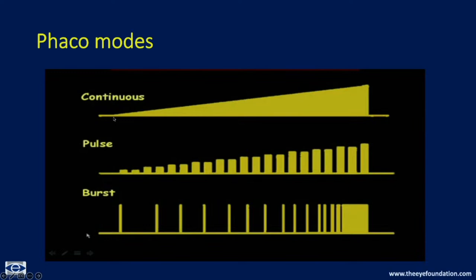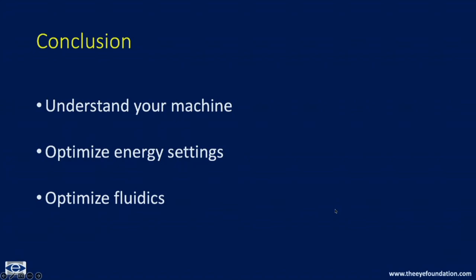In normal continuous linear mode, power starts from the minimum and goes to the preset maximum as you press the foot pedal. In pulse mode, power increases per pulse but duty time does not change. In burst mode, power remains the same per pulse but duty time continues to increase. In conclusion, you need to understand your machine and optimize your settings and fluidics to achieve your ideal phaco case.